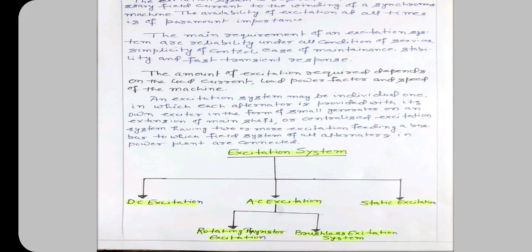Here we can see the block diagram for a DC excitation system. This is an old and conventional method for excitation of alternator fields. In this method, three machines, namely the pilot exciter, the main exciter and the main alternator, are employed. The pilot exciter, as is clear from the figure, is a shunt-wound DC generator, and the main exciter is a separately excited DC generator.